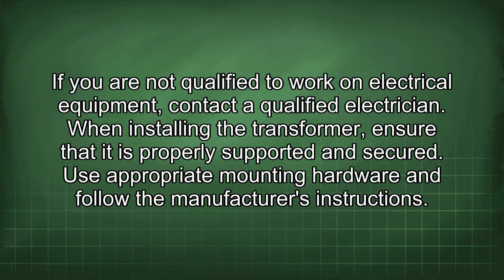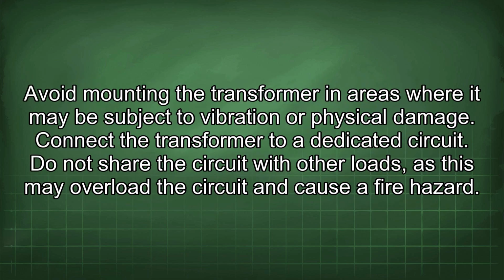When installing the transformer, ensure that it is properly supported and secured. Use appropriate mounting hardware and follow the manufacturer's instructions. Avoid mounting the transformer in areas where it may be subject to vibration or physical damage. Connect the transformer to a dedicated circuit. Do not share the circuit with other loads, as this may overload the circuit and cause a fire hazard.